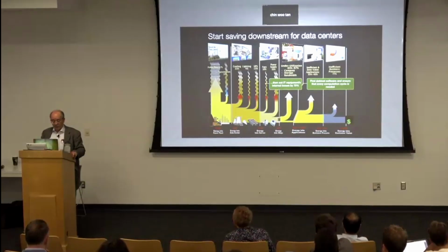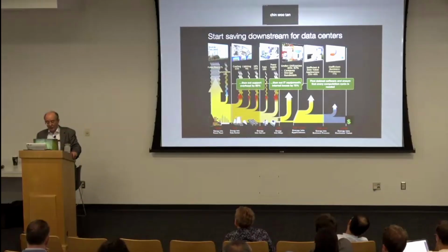And the servers will need a lot less cooling and power supply, both doable in smarter ways. And we could even save half the utility losses by using fuel cell trigeneration, cheaper than the power supplies it displaces. So when you multiply these savings from downstream to upstream, you just cut the total energy use by at least 2 orders of magnitude.